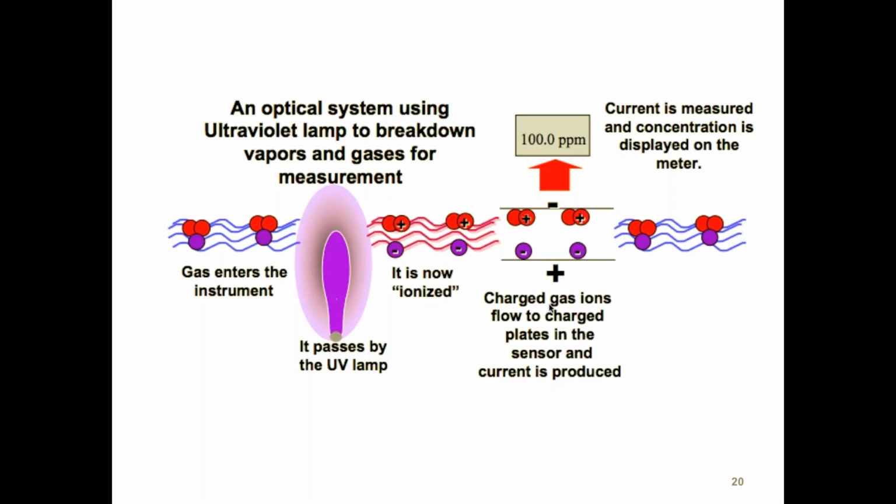Well, it's nice from one perspective because it'll measure a specific gas out of a catalog of gases very accurately. But on the other hand, if it's a mixture of gases, it's a little bit less useful, because if you have MEK, but you're also using acetone and you're also using toluene in that environment, well, now you don't have a table for that, right? So it becomes a little less useful. You can use it to measure kind of intuitively total VOCs to see what the combined level might be.